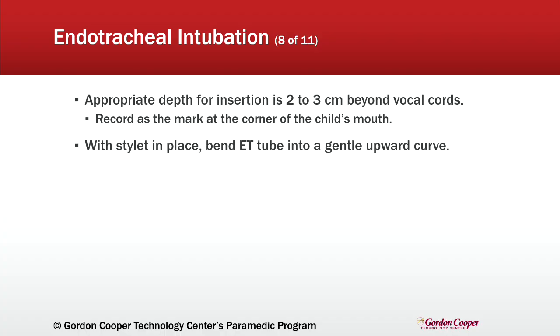A general rule is to insert the tube to a depth that is 3 times its inside diameter. So to get you in the ballpark, depending on your tube size, you'll just multiply that by 3, and that should get you pretty close to the depth that your tube should be.